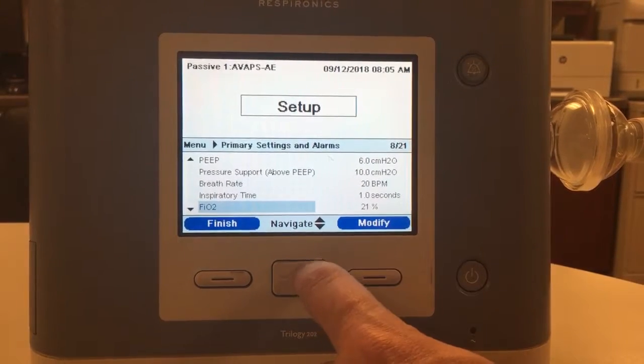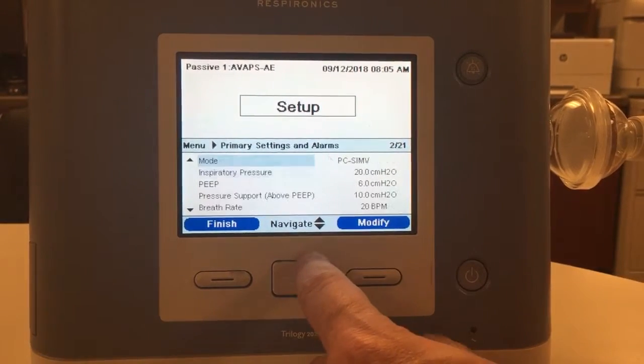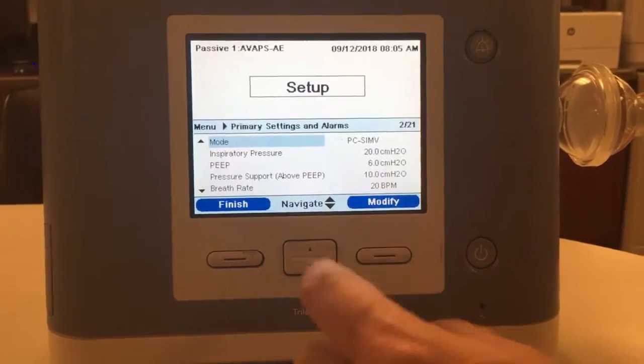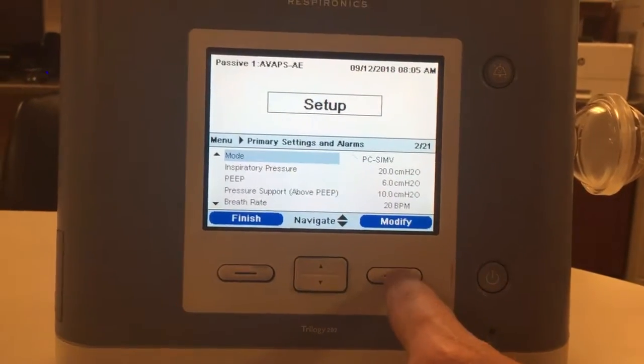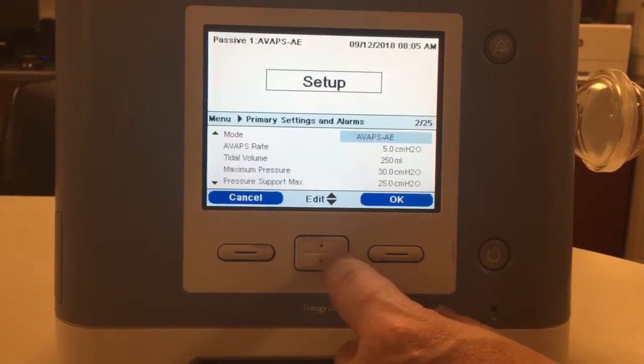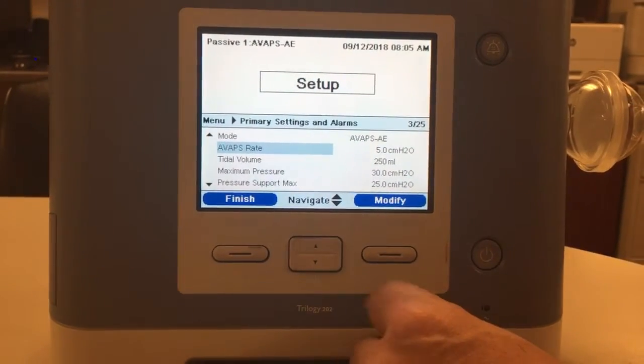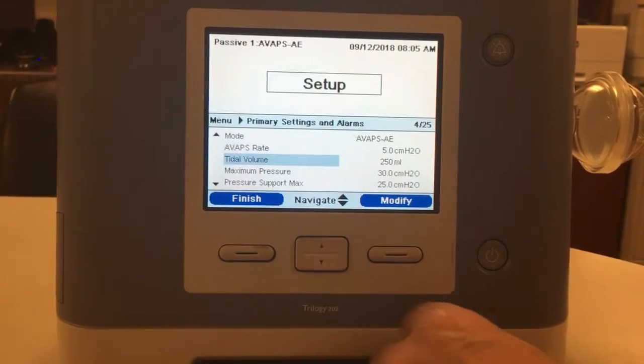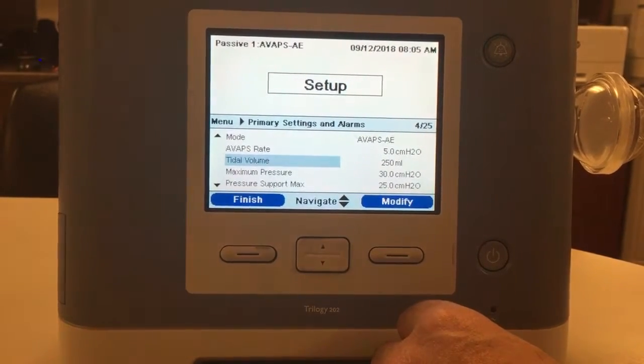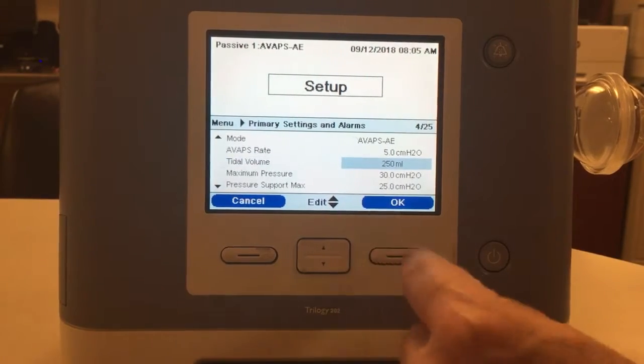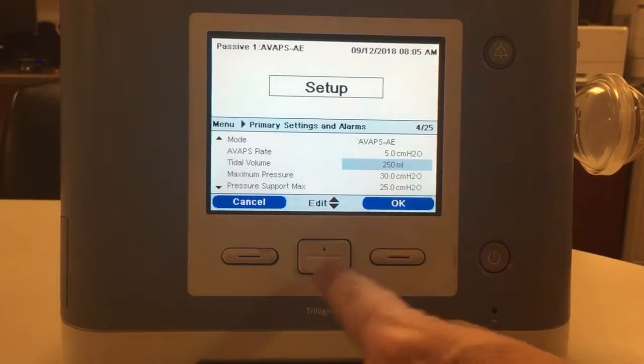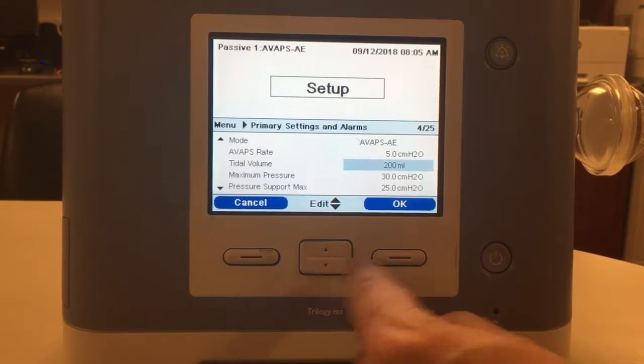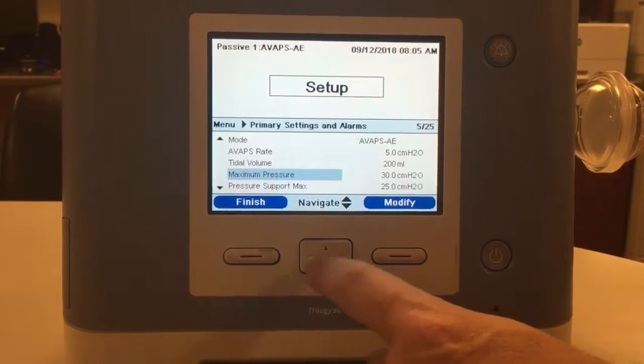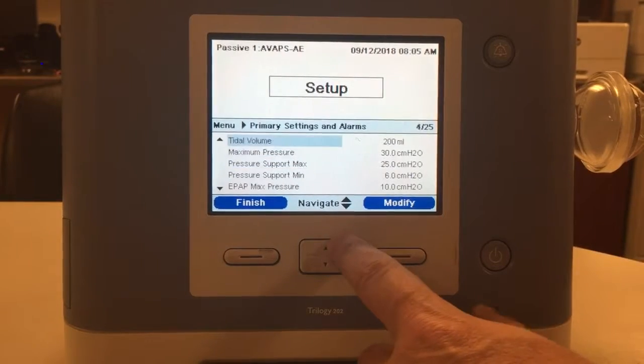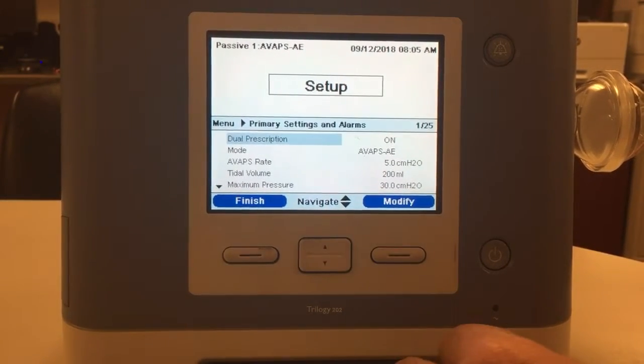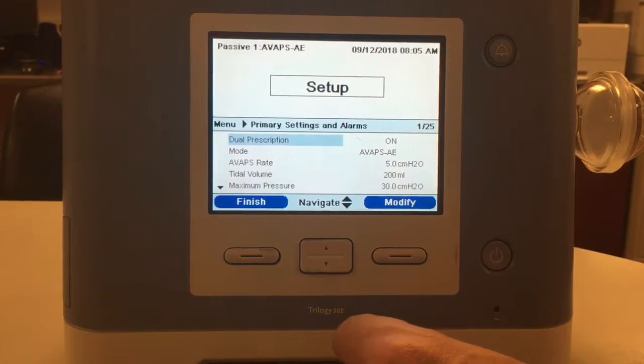And that's set. Let's go back and change the ventilator mode back to AVAPS AE, because the patient is doing well on that. So of course, we would hit modify and AVAPS AE. So now you're back to AVAPS AE. In this case, though, the doctor does want to bring down the tidal volumes. He thinks they're a little high. You would scroll, like I said, modify, and come down to 200. And that's how you would change any settings or modes in the Trilogy 100, 200, or 202 ventilators.